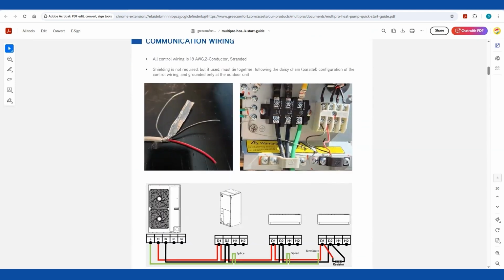This is a little bit more on the wiring. This is the outdoor unit's terminal block for your L1 and your L2 and your ground. And then over here is your D1 and D2 and your G1 and G2. We can talk more about that later on. But D1 and D2 is our communication circuit to our indoor units.